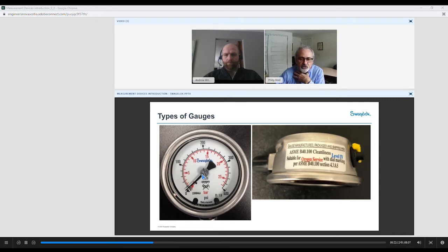You can see how the front is crimped onto this gauge, and it uses a polymeric lens versus a glass lens. So if this gauge is cleaned to oxygen cleaning, and anything over about 23.5%, you should be using oxygen cleaned components. So this gauge is manufactured and packaged in accordance with ASME B40.100 cleanliness level 4, suitable for oxygen service, and the dial markings are as per ASME B40.100 as we discussed.